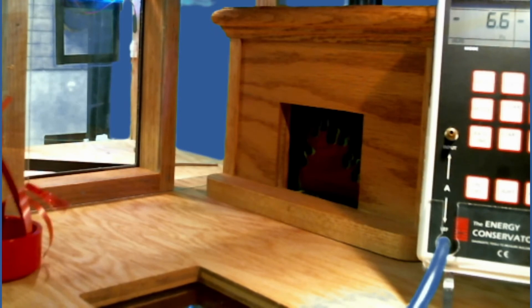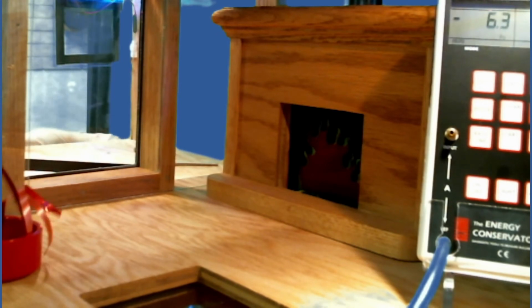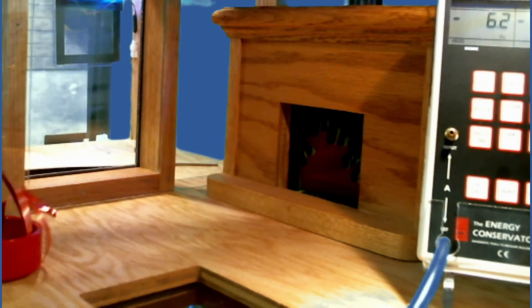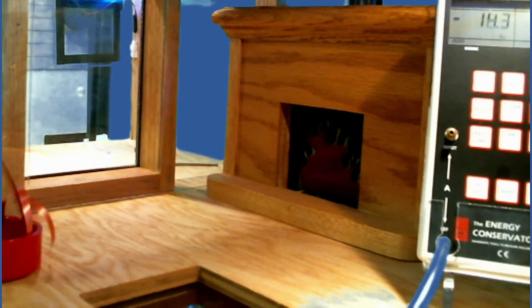So I'm going to go and check this bathroom door, the master bathroom. I'm going to close this door back. I'm sorry, can you see that? Yeah, you can see that door, on the left side of your picture there. Close that door back. And now I close the door. Look what happened to the number now. When we closed that door, it went to -14.